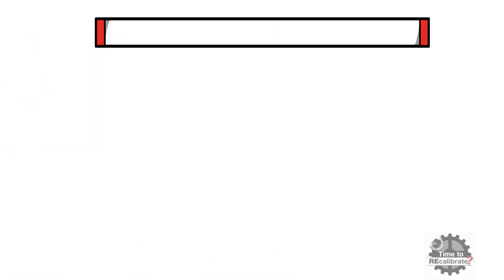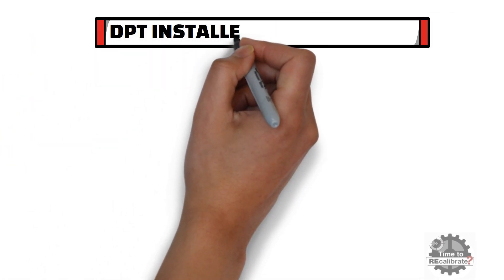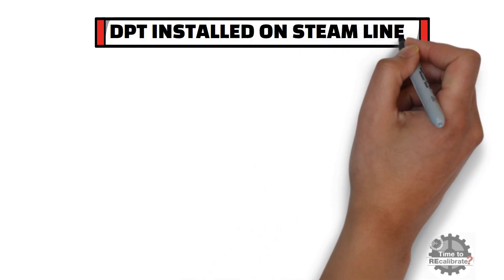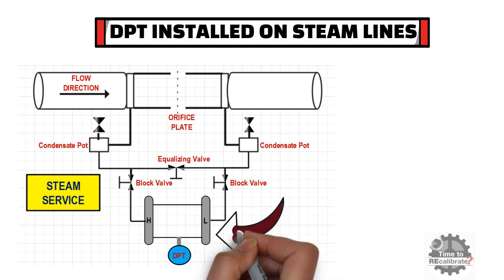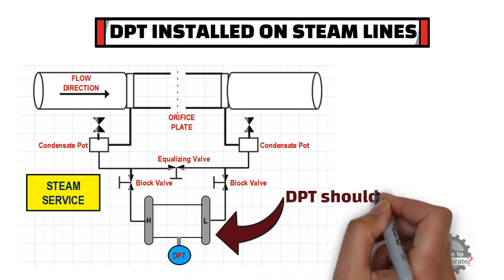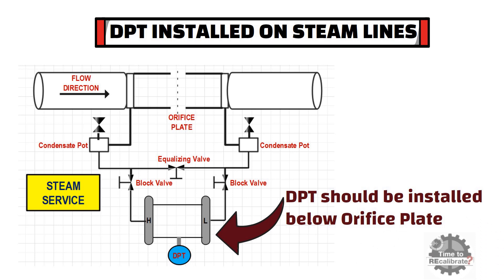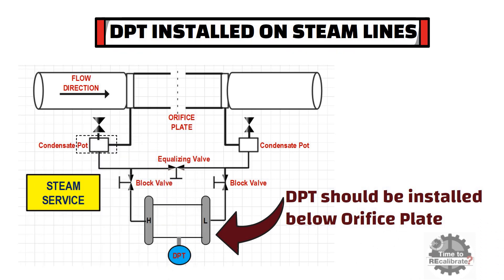Now let's take one more situation when a differential pressure transmitter is installed on steam lines. As you can see, for steam lines, the DP transmitter should be installed below the orifice plate with condensate pots. Both the pots should be installed at the same level.